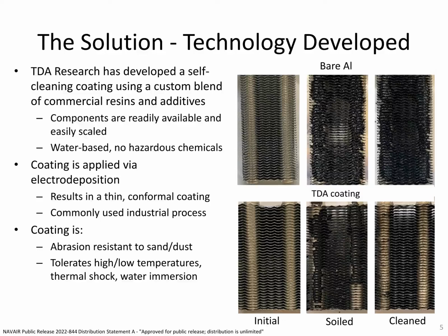Here we show a bare aluminum heat exchanger and a coated heat exchanger that have been fouled with an artificial soil, in this case a mixture of synthetic hydraulic fluid and AFRL test dust. We can see that the coated heat exchanger has lower fouling, meaning that less of the artificial soil adheres to the heat exchanger fins. After cleaning with a low-pressure water rinse, we also see that the coated heat exchanger is much easier to clean than the bare aluminum.